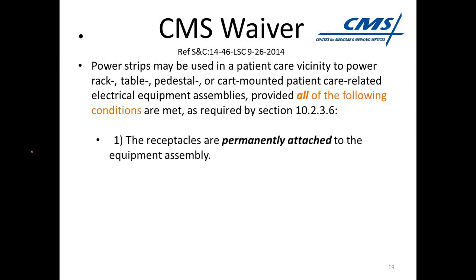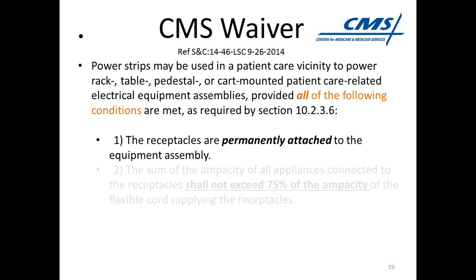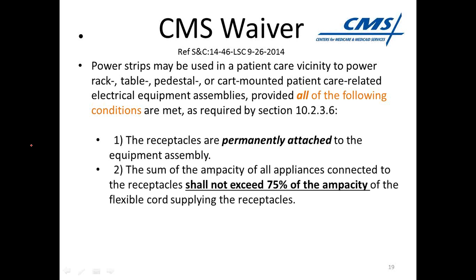The first one, they have to be permanently attached to the equipment assembly, which, based on this waiver, actually means it can be attached to an IV pole. It works just as well. You need to check and make sure that everything plugged into this power strip does not exceed 75% of the current carrying capability of the flexible cord.